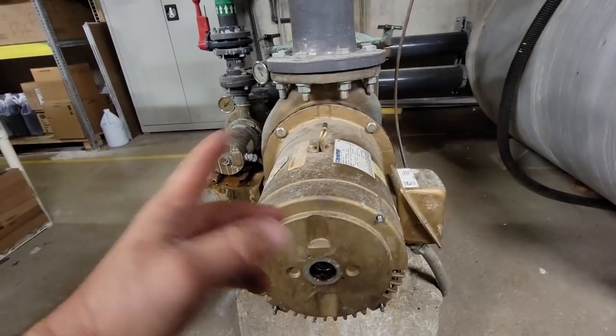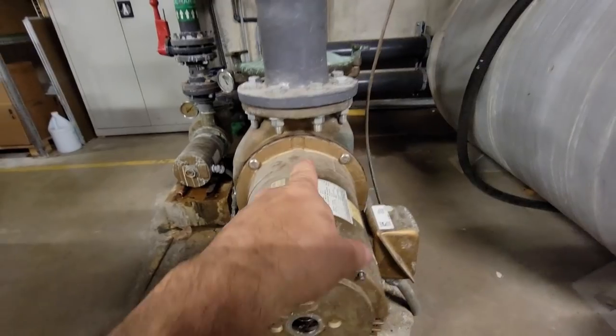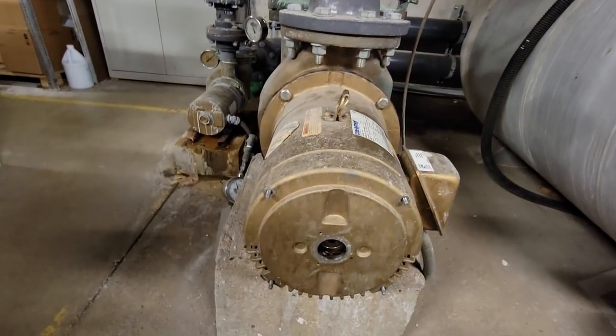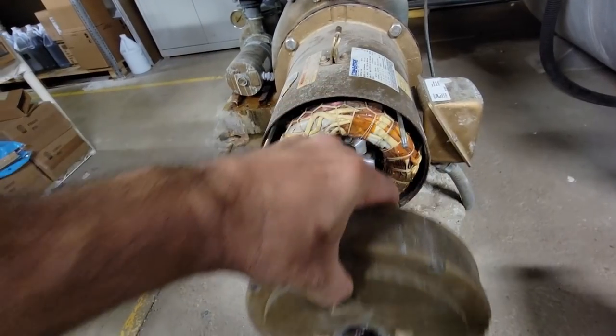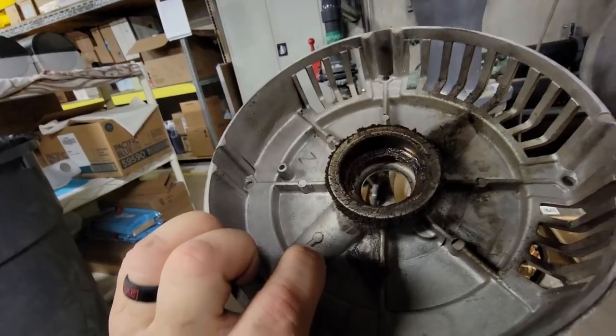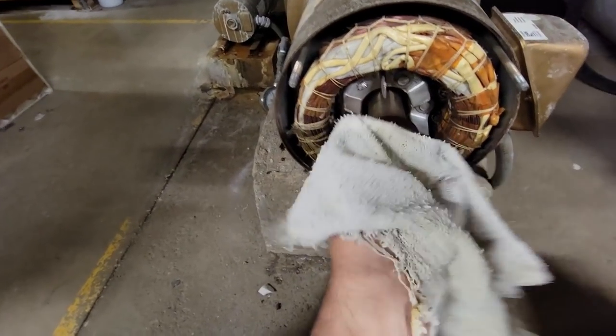I can yank this out fairly easily; there are valves here and there. I'm going to try to avoid taking it apart because I don't know what I have for a seal or gaskets — this was totally unplanned. I was supposed to just make sure that heat exchanger was set right, because the building automation system doesn't work. Let's get this end cap off — you can see the bearing housing.